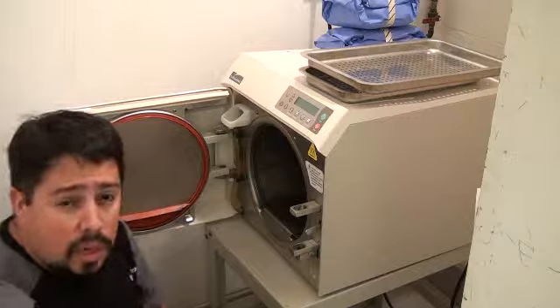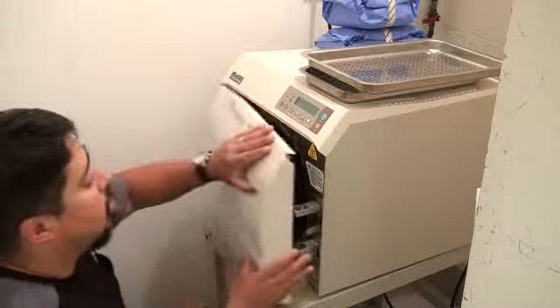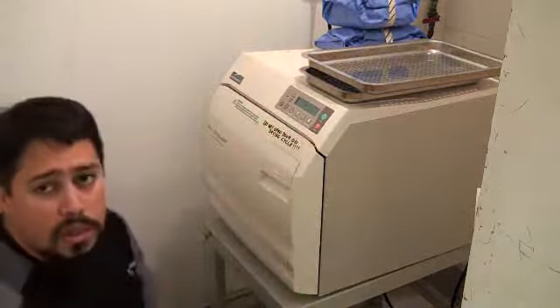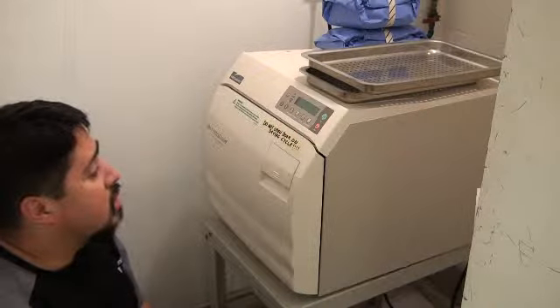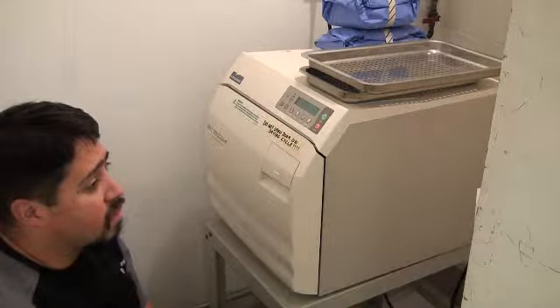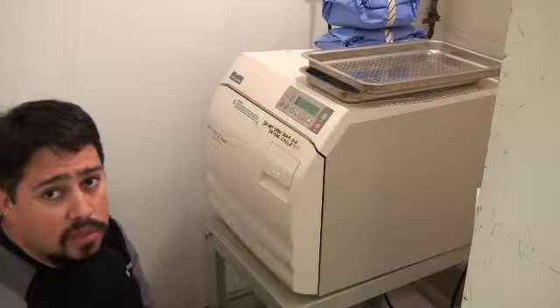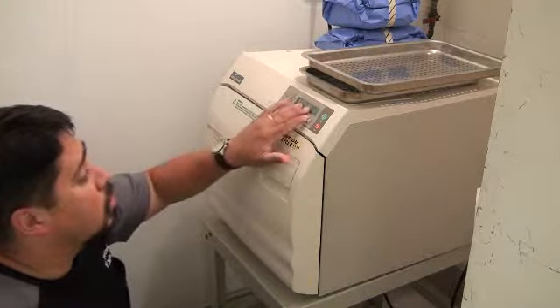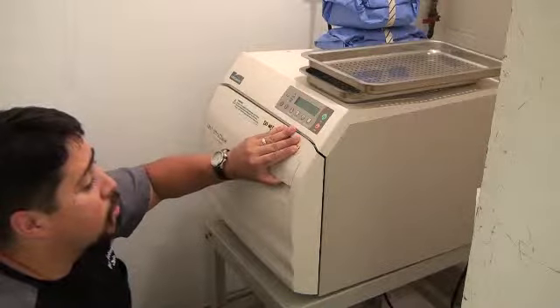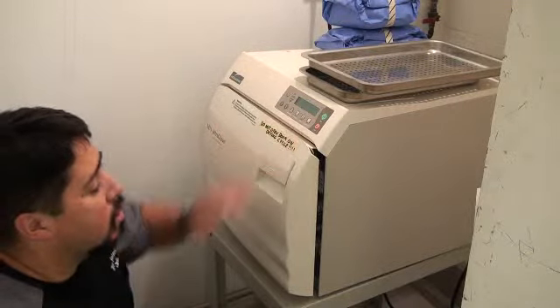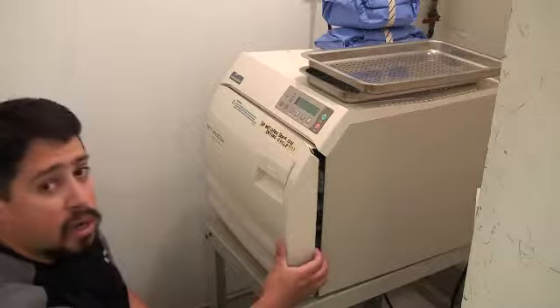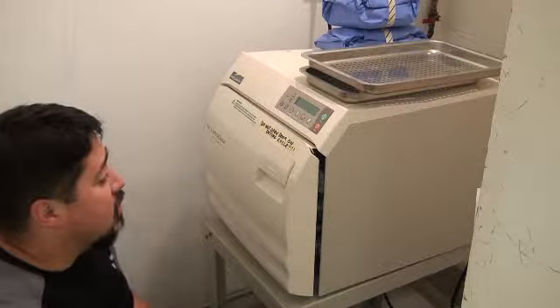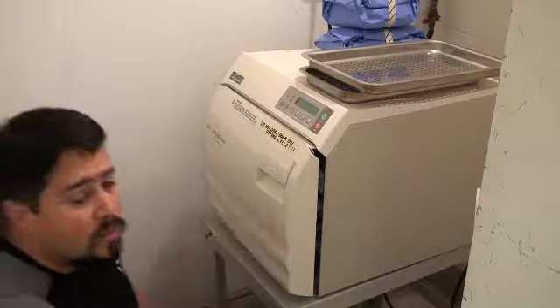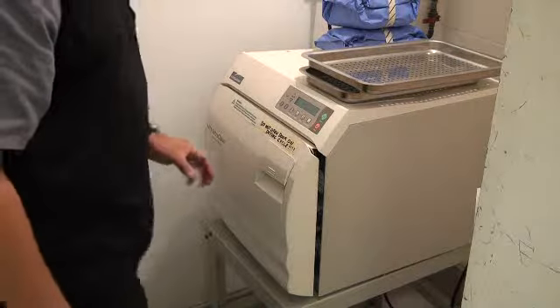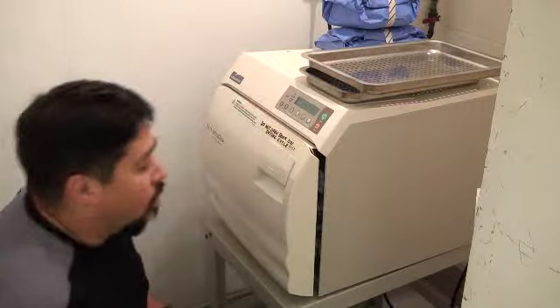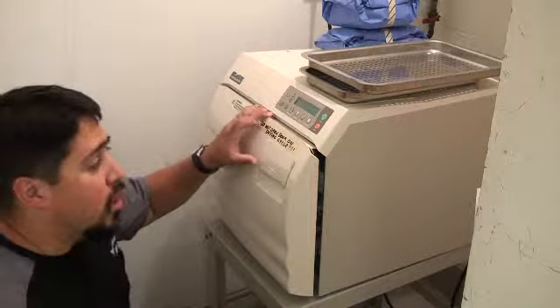Let's see. Once the autoclave, I'll show you here. Typically, it's closed during its cycle of operation, but once those 3 to 15 minutes of sterilization have happened, the autoclave gives a little warning and the door opens. It will pop the door open. You can't actually open it any further than what it has cracked. This, combined with the heat, allows a lot of the water vapor inside the autoclave to evaporate.